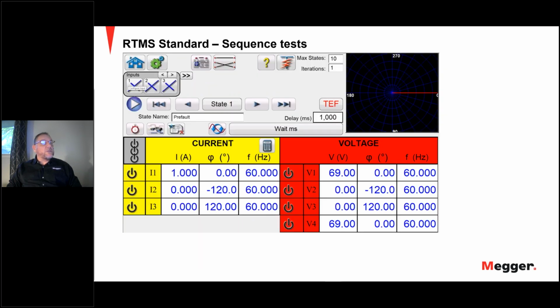The sequence test is used for testing reclosing type relays, setting up multiple vectors and general multi-state sequencing. It also includes a transient earth fault simulation, including intermittent transients.